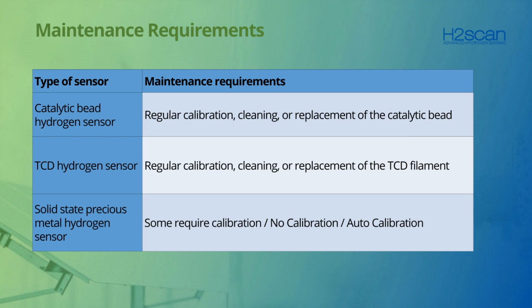Solid state precious metal sensors have a variety of requirements depending on which one you choose. The frequency of calibration is also dependent on the same factors. However, there are some solid state sensors that do not require field calibration. They simply are replaced after the expected life. Some will require calibration, and then there are other solid state sensors that calibrate themselves or perform what we call an auto calibration.